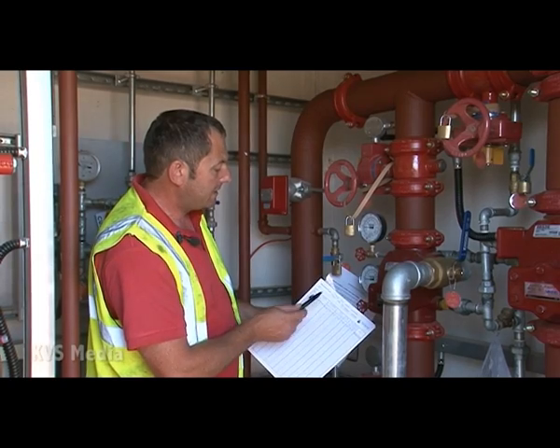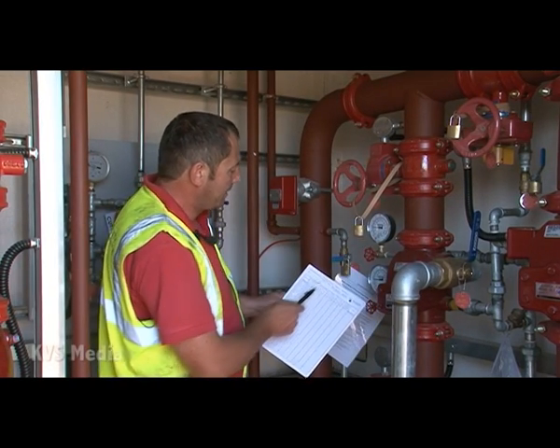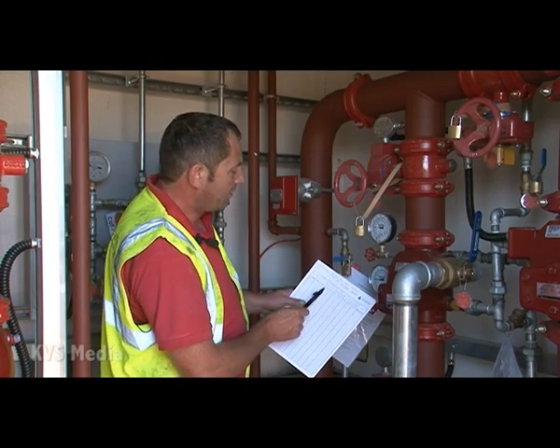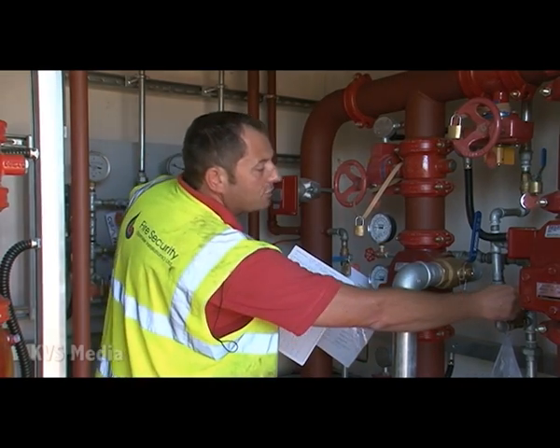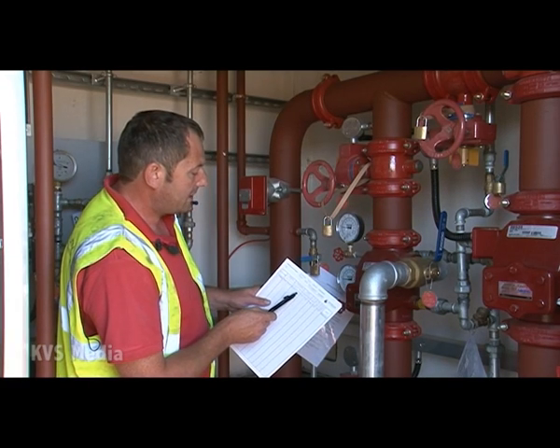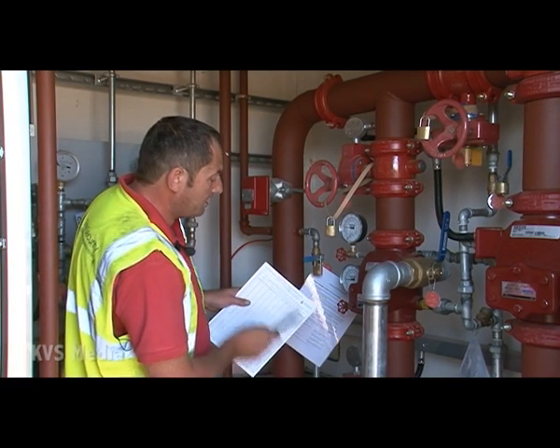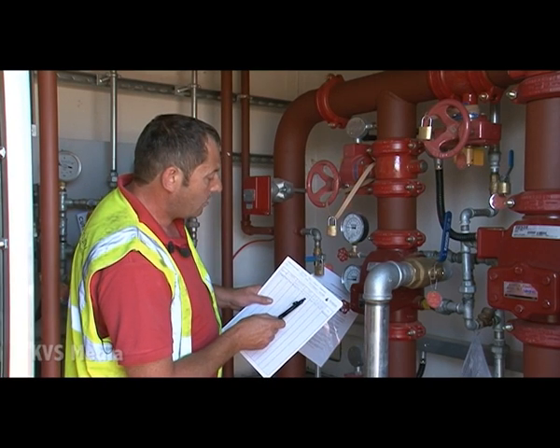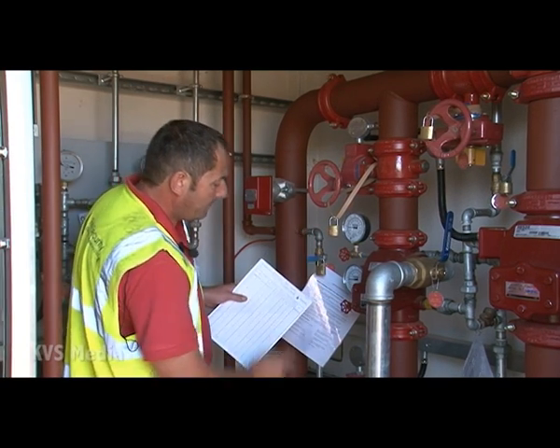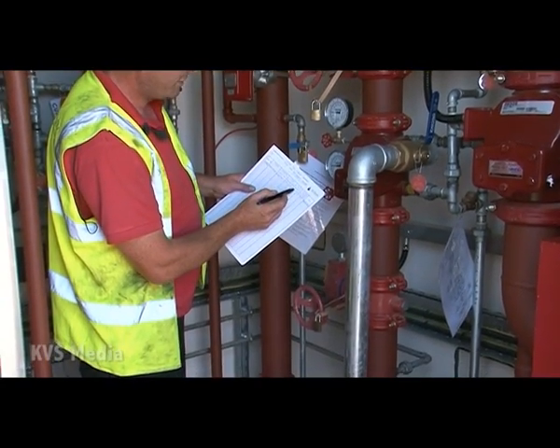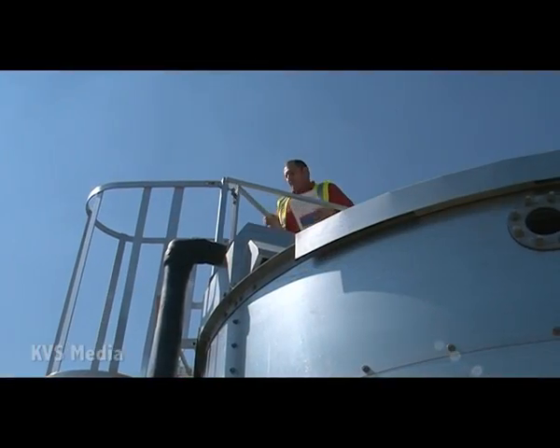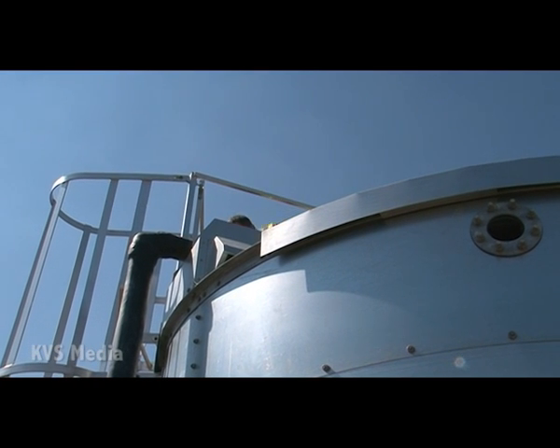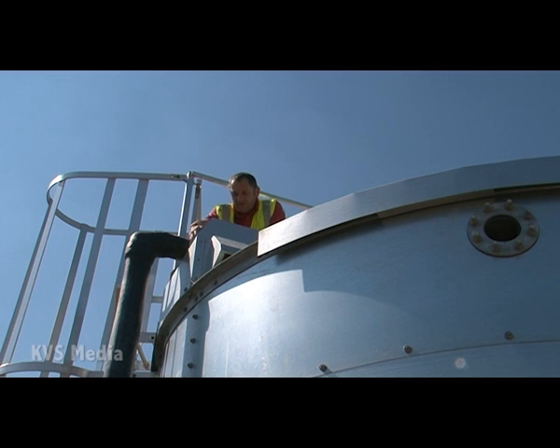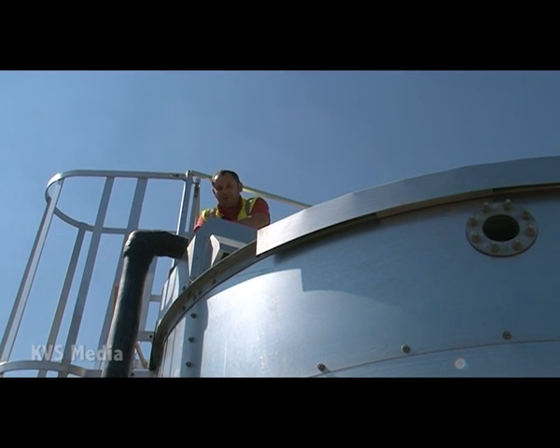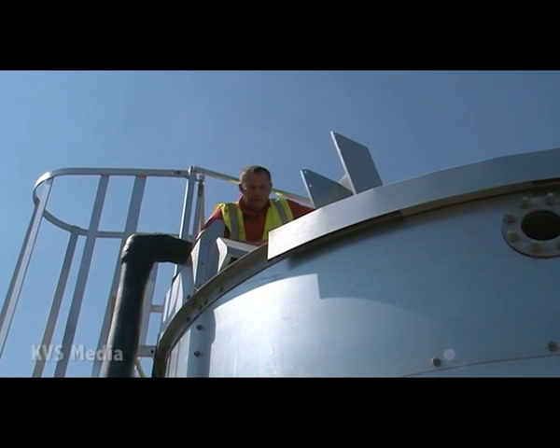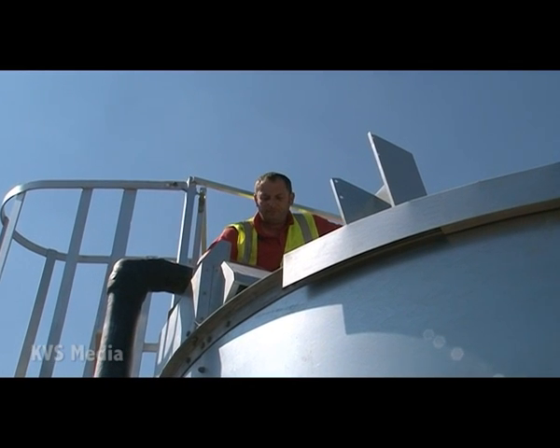So we've recorded the date, we've recorded the before pressure, we've recorded the after pressure, we've recorded the time taken for the gong to ring. The gong worked satisfactorily, stop valve is secured open, all other water supply valves are open, water storage tank full, and physically open the hatch and check the water level is full.